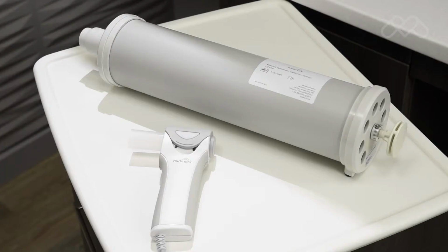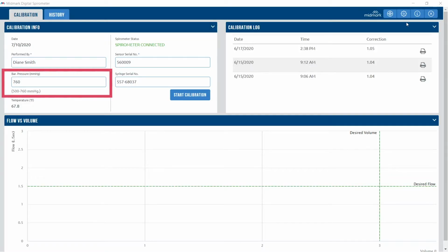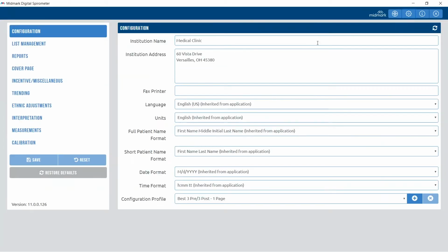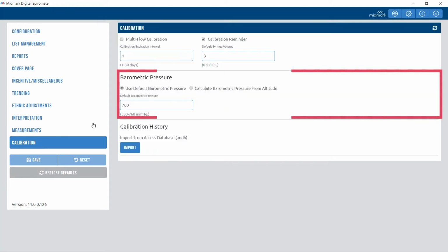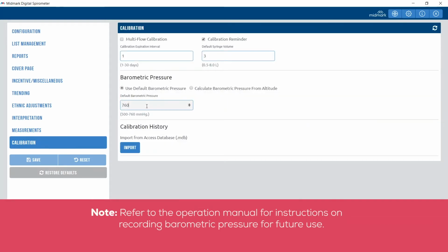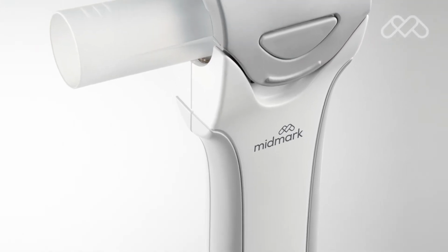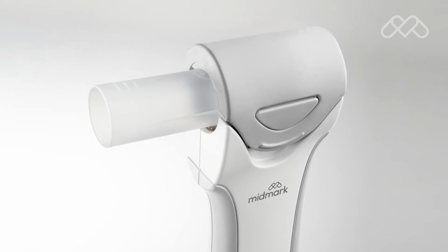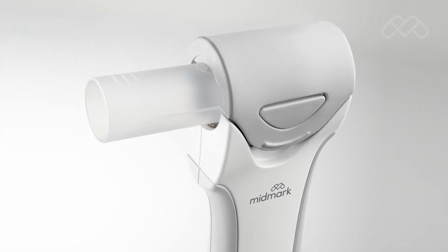Calibrating the digital spirometer requires a 3-liter calibration syringe. The barometric pressure must be entered prior to the first time you calibrate the spirometer. Refer to the operation manual for instructions on recording barometric pressure for future use. The digital spirometer must be calibrated using a digital spirometer disposable mouthpiece.